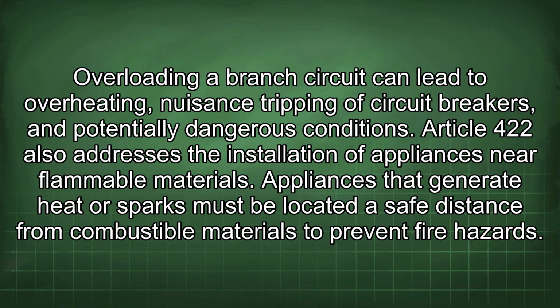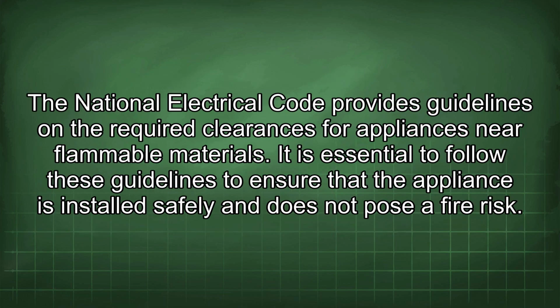Article 422 also addresses the installation of appliances near flammable materials. Appliances that generate heat or sparks must be located a safe distance from combustible materials to prevent fire hazards. The National Electrical Code provides guidelines on the required clearances for appliances near flammable materials. It is essential to follow these guidelines to ensure that the appliance is installed safely and does not pose a fire risk.